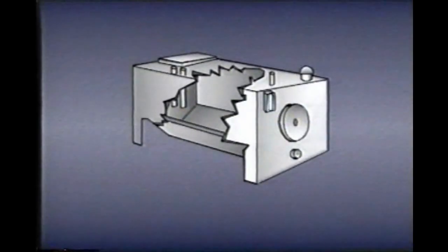The reservoir's dished bottom collects the dirt, and an end cover permits occasional clean-out. A drain allows sampling of the fluid. A gauge indicates the fluid level. A filler cap includes a built-in breather to let air escape. A sturdy plate provides a place for mounting the pump and motor.